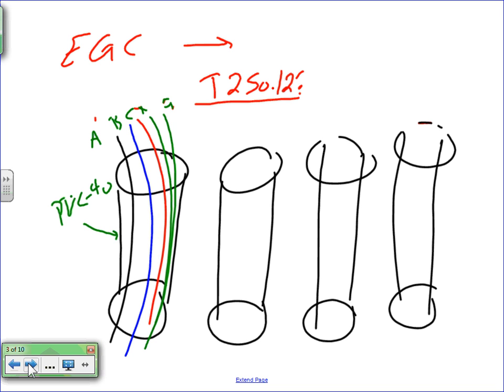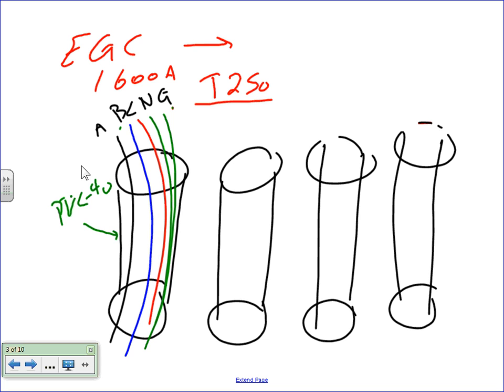And then I want to size the equipment ground and conductor. Which color should I use? I want to size the equipment ground and conductor. Let me erase these A, B, C, D, and a neutral. This space should be A, B, C, neutral, and a ground. Now, if I'm using PVC, I need an equipment grounding conductor. If I am to size an equipment grounding conductor, here's how we're going to do it. You're going to take the 1600 amp to 250.122.